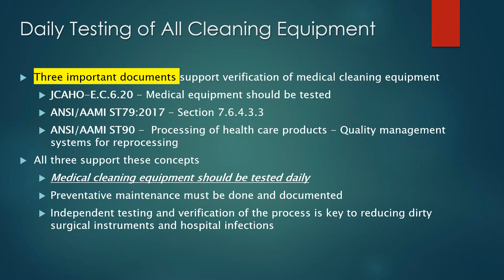And so, keeping all of those things in mind, the Joint Commission EC 6.20, that's medical equipment, should be tested. Again, ST79, Section 7 heavily speaks to that. And then, as I mentioned before, ST90 is a quality document, quality management systems. And of course, testing to make sure that your equipment is working properly is going to add quality to your department and quality to your process. And they all support the same concept. Medical cleaning equipment should be tested daily. Preventative maintenance must be done and documented. And independent testing and verification of the process is key to reducing dirty surgical instruments and hospital infections.